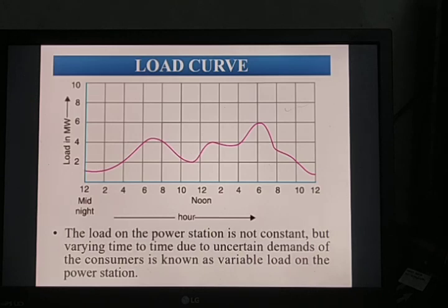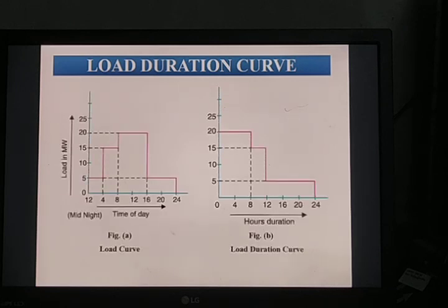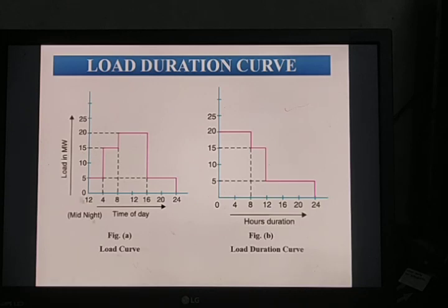The monthly load curve can be taken from the daily load curve of a specific month by calculating the average value of power. Next is the load duration curve. The load duration curve can be plotted from the ordinary load curve — the maximum load is plotted on the left-hand side and decreasing loads are represented on the right-hand side in descending order.